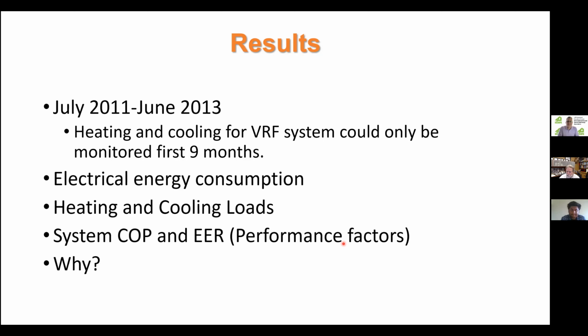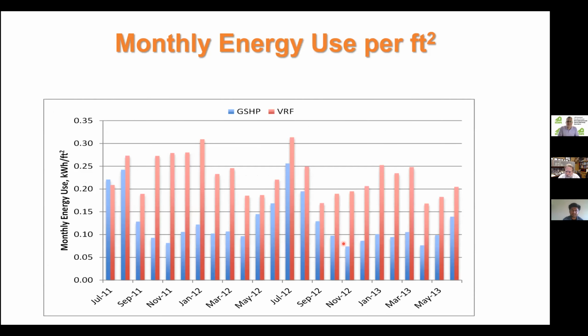And then we're going to discuss why this happened. So the presentation is in the same order that we did the research. First we'll look at the electrical energy usage, and we can make our own judgments based on that. Then we look at the loads, and finally the system performance metrics. So the monthly energy used per square foot is here. You can see that in July of 2011, the ground source heat pump system used a little bit more kilowatt hours per square foot. And every month after that, the VRF always used more energy.